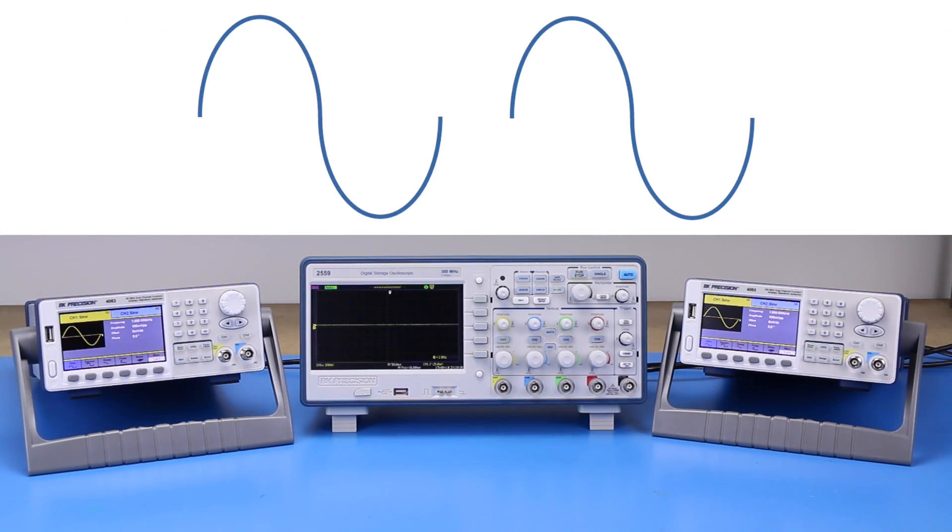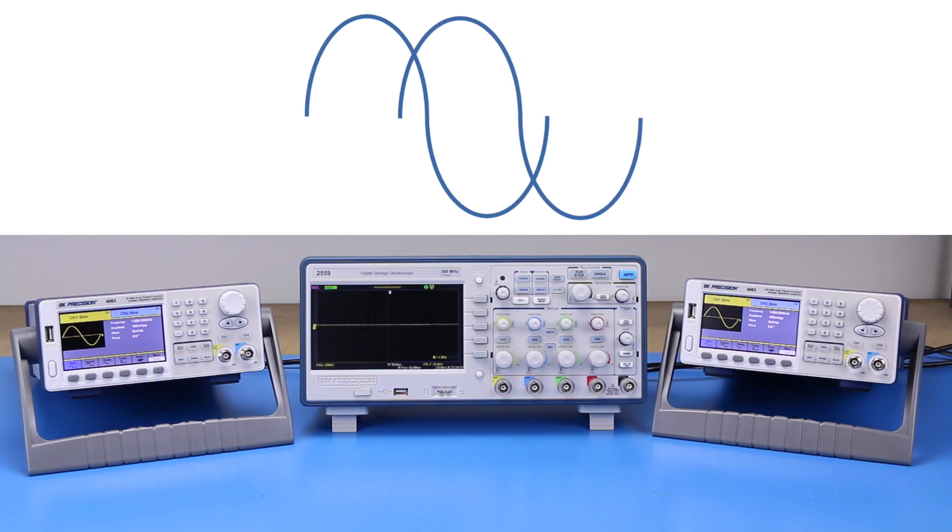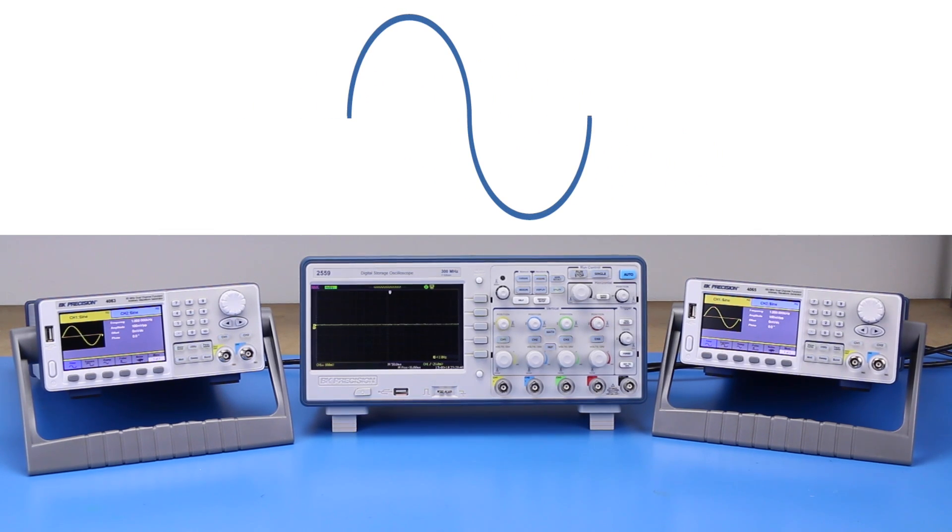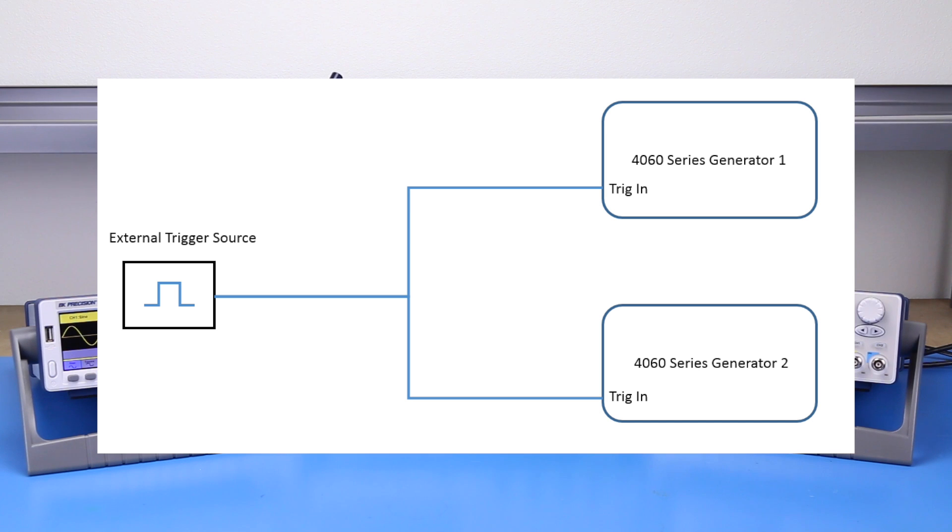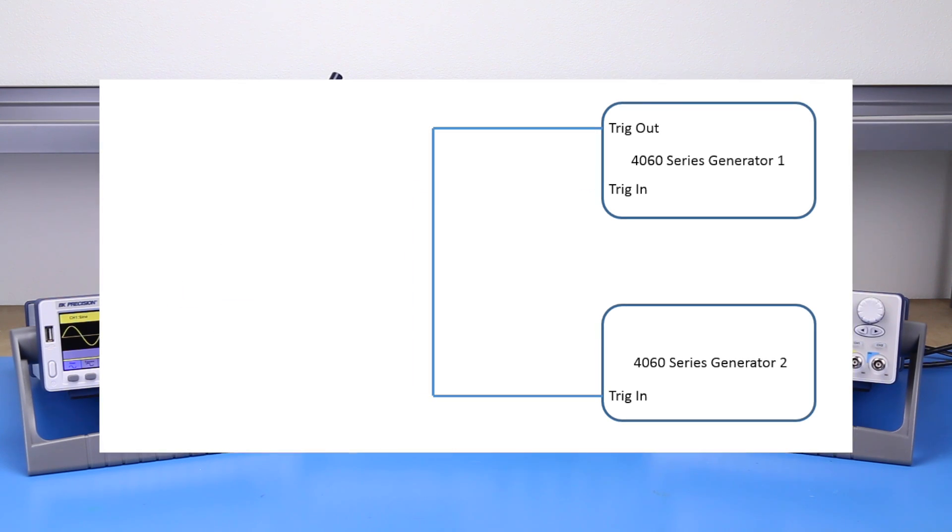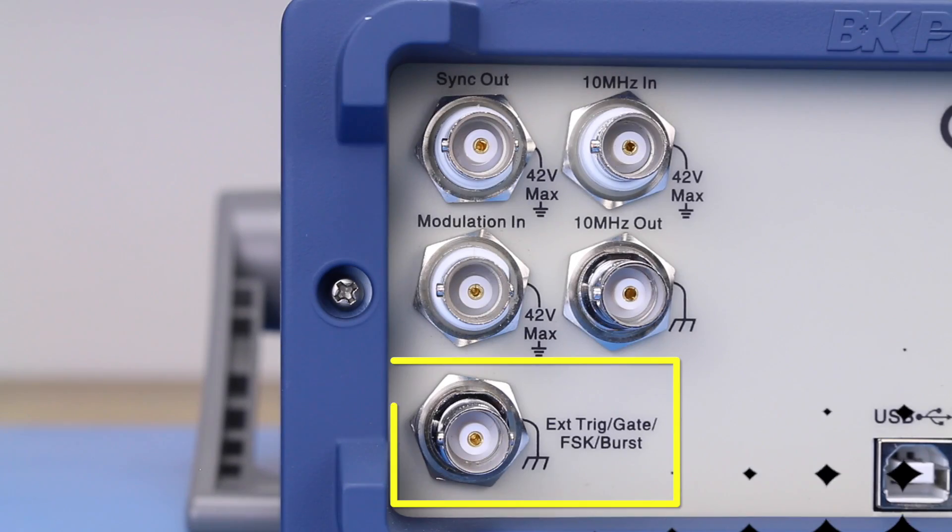The signals can then be aligned by using the burst function and each unit's external trigger BNC connector. The trigger could be from an external source or generated from one of the generators. For this example, we will use unit 1 to generate the external trigger.